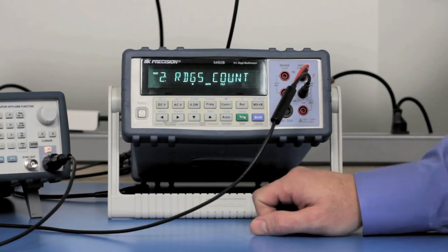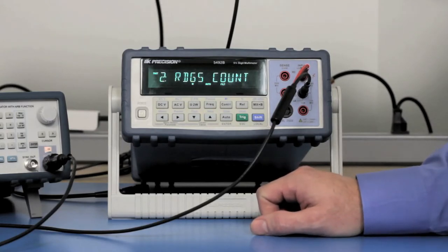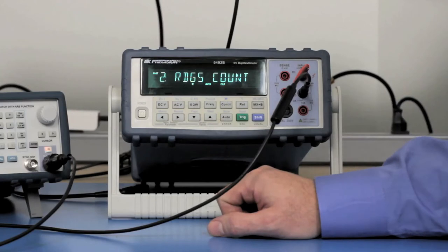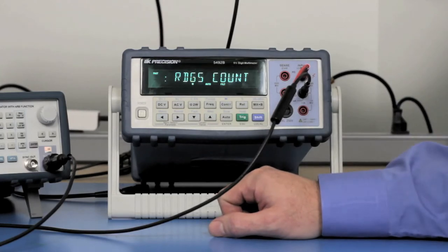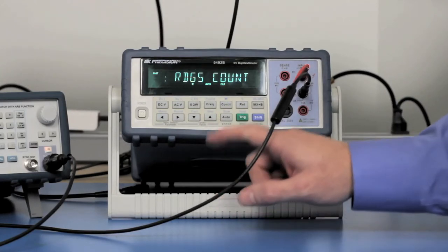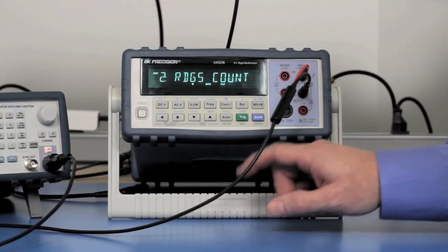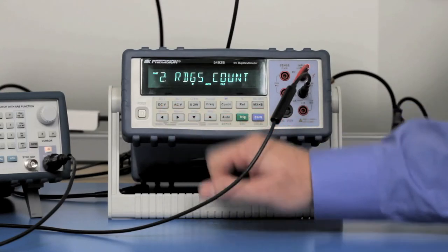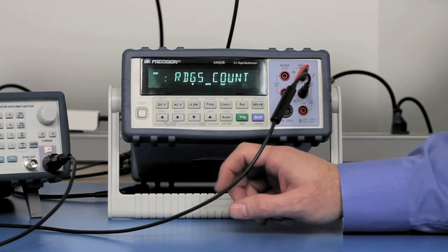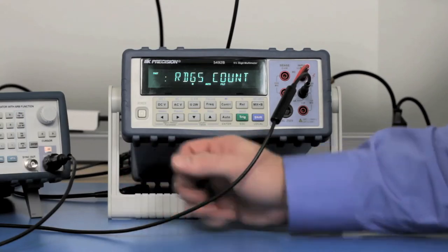Once the 5492B is in the buffer storage mode, you're going to see this little asterisk right here underneath the G telling you that it's in that mode. Now the unit is ready to go, and as soon as I press shift left arrow, the 5492B will start to record. But before we do that, I'm going to show you how I'm going to generate the signal and what we should expect to see.